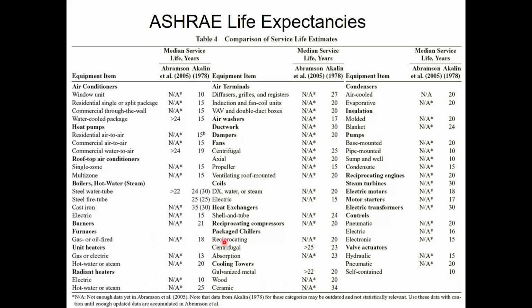If you have unit heaters out in your warehouse or manufacturing plant, right, or just a general storage area in your small office building, look at those guys. For a gas unit heater, 13 years is the average, right? It's fairly short, right? So look at some of these things and kind of get an idea of when I might have to replace it. If I had a large centrifugal fan in my air handler, 25 years, right? For you guys that do chillers, 20, 23 years. Cooling towers, 20 years, right? So this is a good cheat sheet to have, like I said, sometimes it's longer, sometimes it's less, but this just gets you in the ballpark.